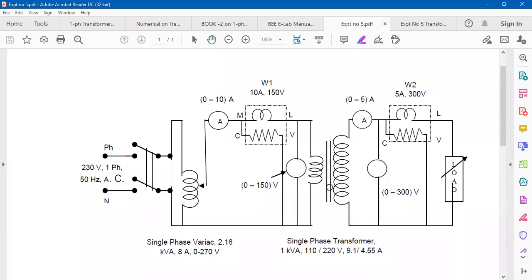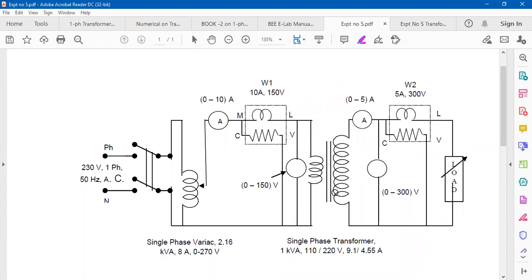The Direct Loading method is used to calculate the efficiency and voltage regulation of a transformer. The transformer used here has a rating of 1 kVA, 110V/220V. On the primary side, 110V constant is applied, and on the secondary at no-load, 220V is obtained. It is a step-up transformer with fewer turns on primary and more on secondary. Using Direct Loading, voltage regulation and efficiency are found by directly putting load on the secondary.